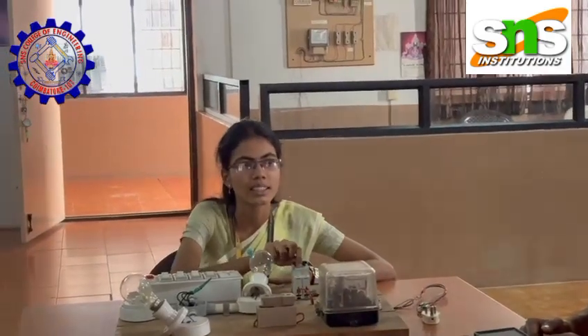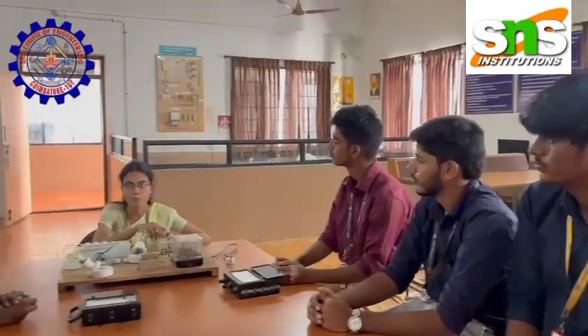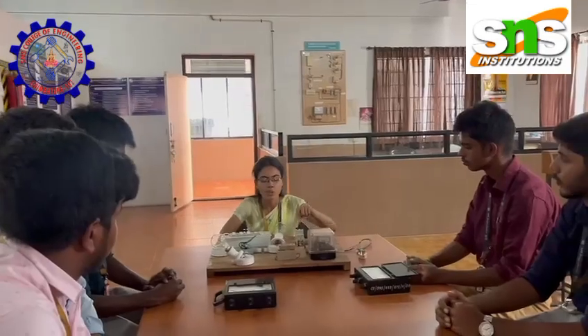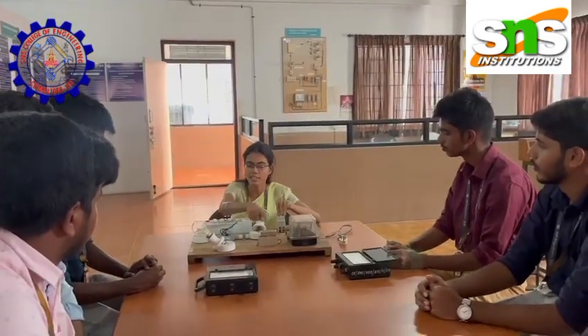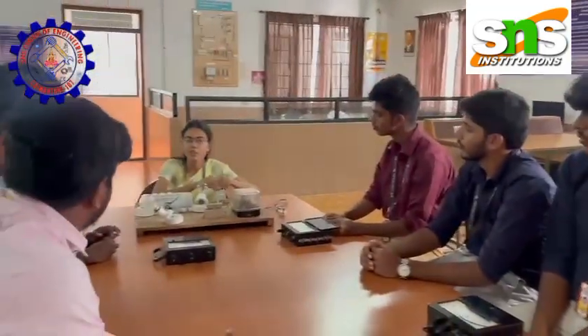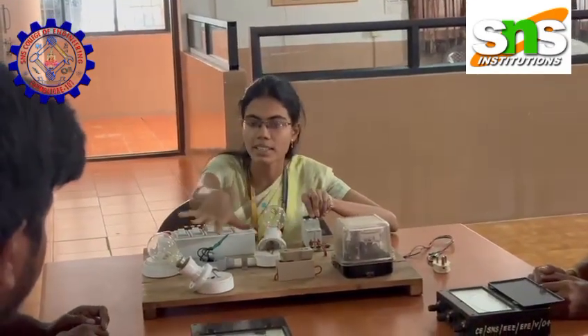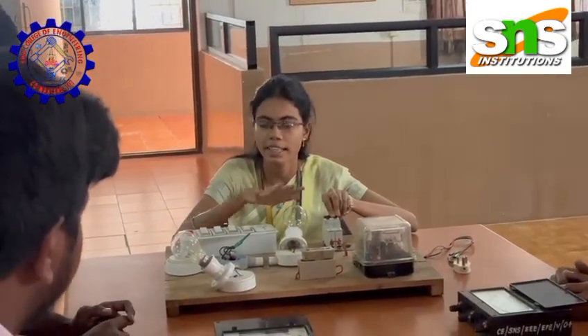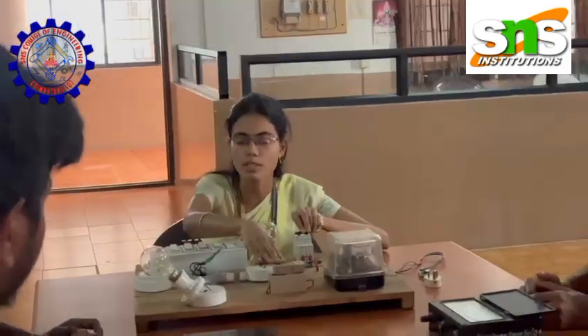Instead, we will always switch off this MCB. The MCB means the circuit breaker. So we always break this circuit breaker and then check the fuse. So what is the purpose of shutting it down first and then checking the fuse? To stop the voltage. It's not just to stop the voltage. If the circuit breaker is in the off state, there is no conduction to the entire system. The fuse is also for the same application, but if the fuse cannot withstand the capacity, the circuit breaker suddenly trips, so that there is no conduction.